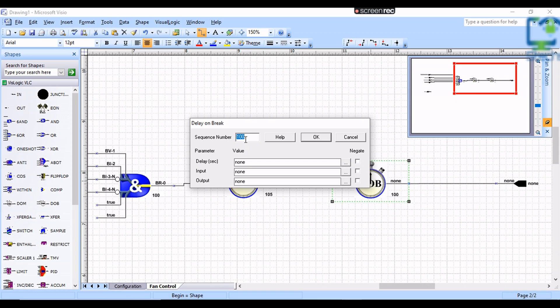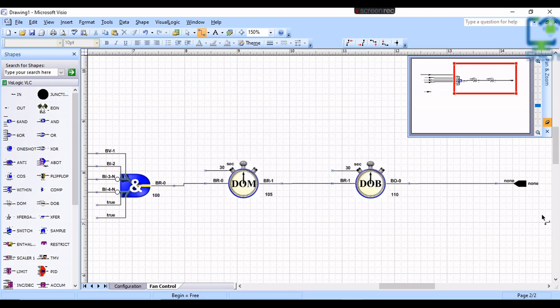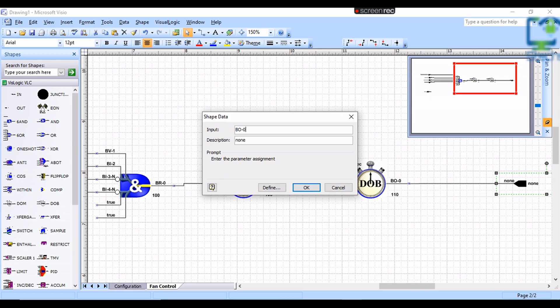In the next timer, the sequence number is changed to 110, and a delay of 30 seconds was added as per the sequence of operation. The input will be BR 1 because it is the output of the DOM functional block. The output I am going to give B0 0, because the fan start-stop command is connected to binary output. Now I am going to connect it to the output block. Then double-click on the output block and add B0 0 in the input column, and for the description I am going to give Fan Command.